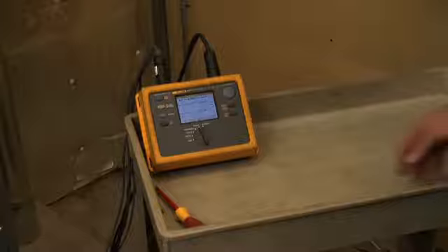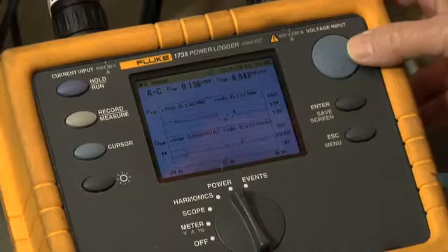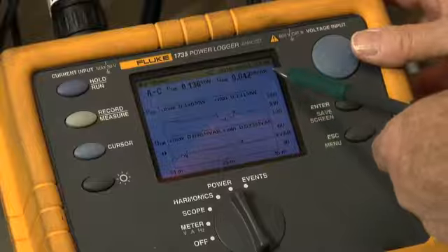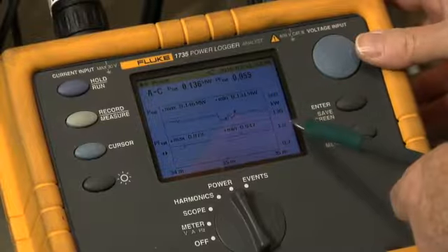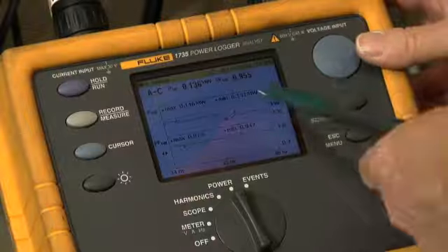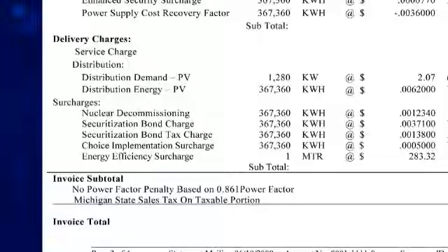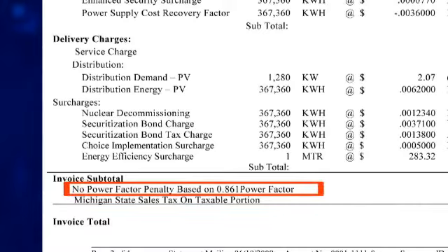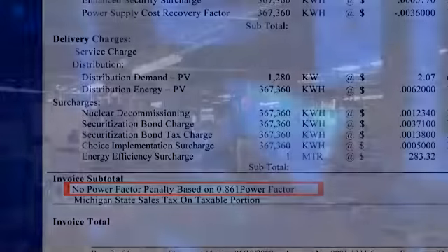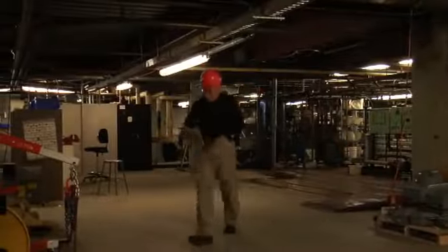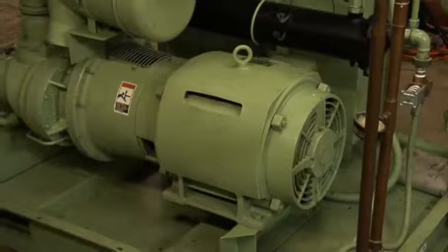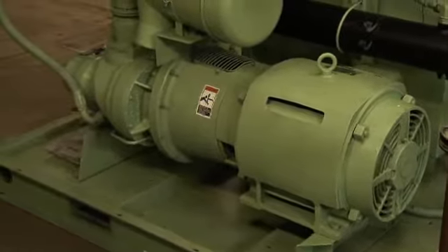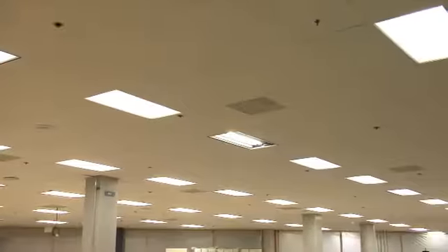When you're done logging, come back, terminate the recording, and check the data on your logger to verify you collected the data you wanted. Review kW, kVA, kVAR, and most importantly, power factor. A decent power factor value is usually 0.9 and above, but it depends on the utility. If power factor is bad, but power demand is low, the utility probably won't charge for it, and it's not worth fixing. If you have bad power factor and high demand, your next step is to find the problem load. Most often, bad power factor is caused by big motors, welders, compressors, or loads that are constantly on, like lighting, especially high-efficiency lighting.